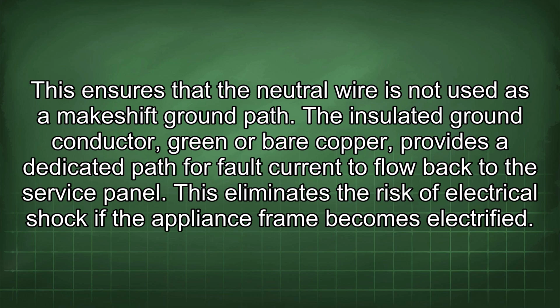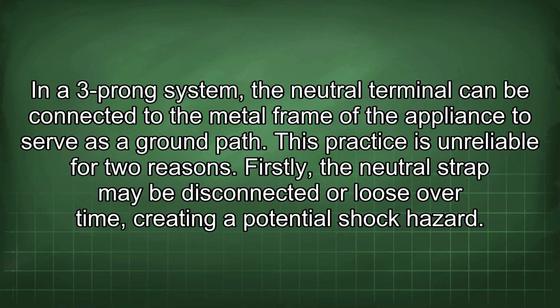The insulated ground conductor, green or bare copper, provides a dedicated path for fault current to flow back to the service panel. This eliminates the risk of electrical shock if the appliance frame becomes electrified. In a 3-prong system, the neutral terminal can be connected to the metal frame of the appliance to serve as a ground path. This practice is unreliable for 2 reasons.